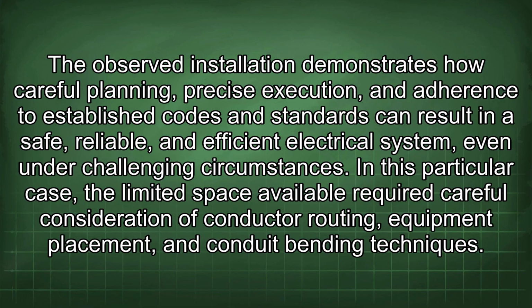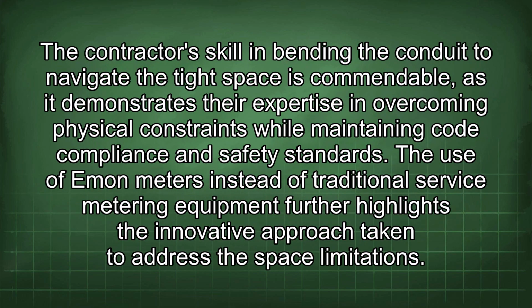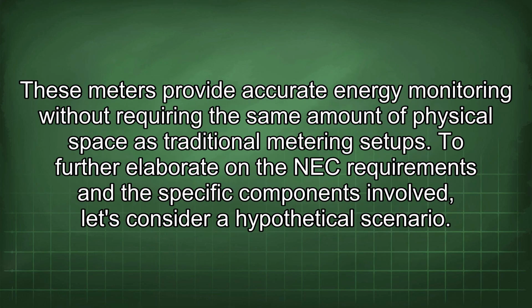In this particular case, the limited space available required careful consideration of conductor routing, equipment placement, and conduit bending techniques. The contractor's skill in bending the conduit to navigate the tight space is commendable, as it demonstrates their expertise in overcoming physical constraints while maintaining code compliance and safety standards. The use of Emon meters instead of traditional service metering equipment further highlights the innovative approach taken to address the space limitations. These meters provide accurate energy monitoring without requiring the same amount of physical space as traditional metering setups.